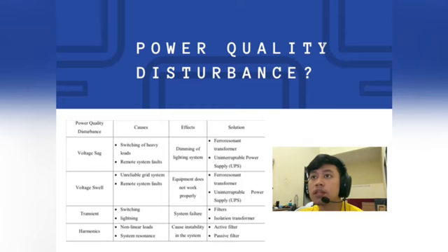Voltage sag occurs when the RMS voltage magnitude decreases to between 0.1 and 0.9, and it lasts for 0.5 cycles to 7 seconds. The causes are the switching of heavy loads and remote system faults. The effect is the dimming of the lighting system. The solution to overcome voltage sag is using a ferroresonant transformer and an uninterruptible power supply, known as UPS. The second one is the voltage swell.